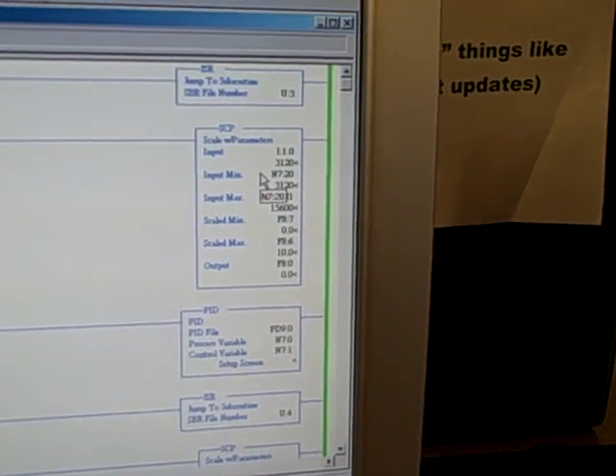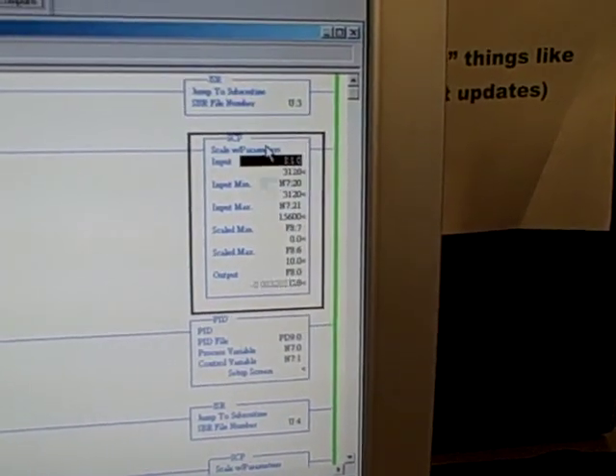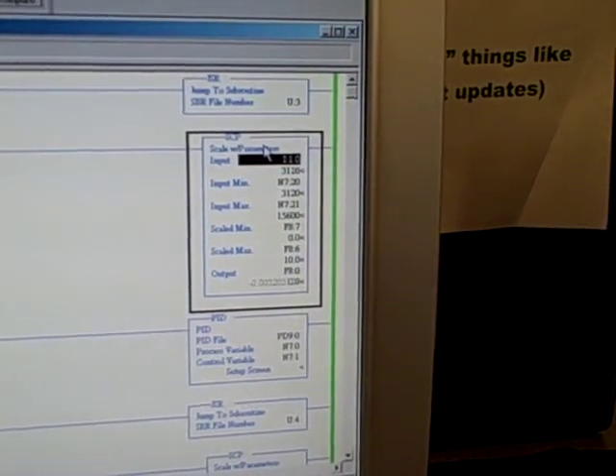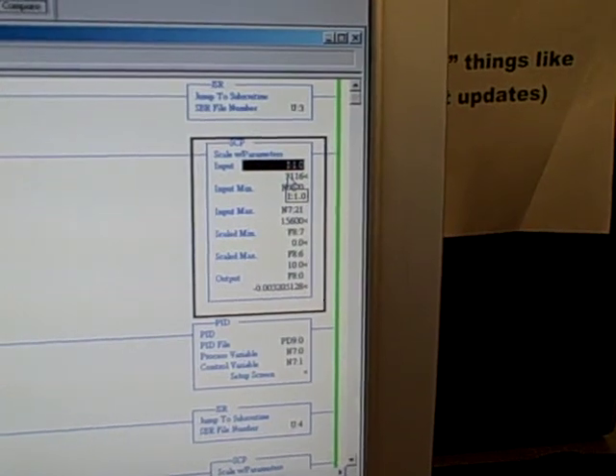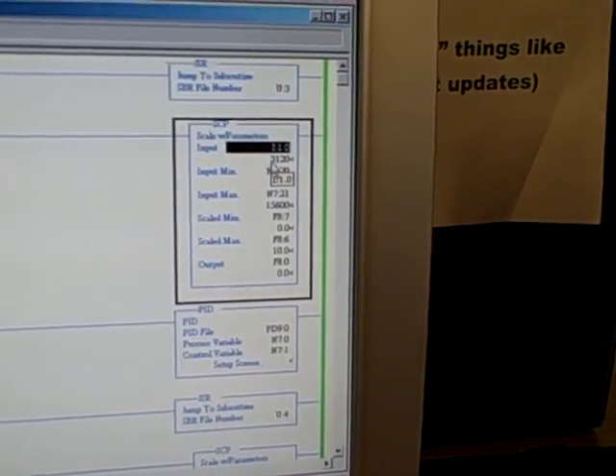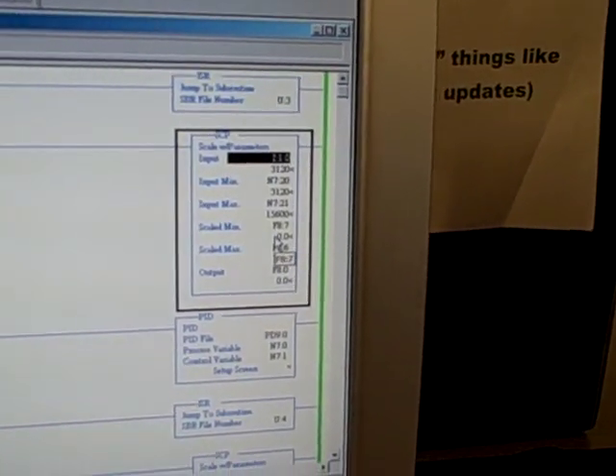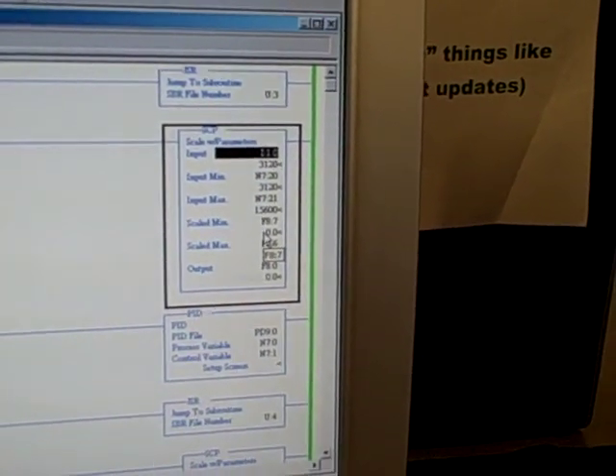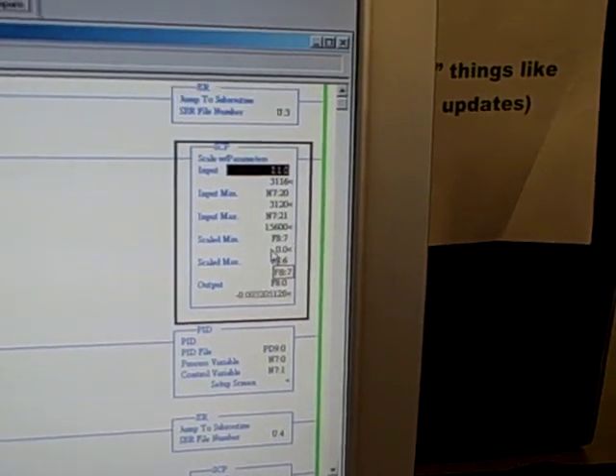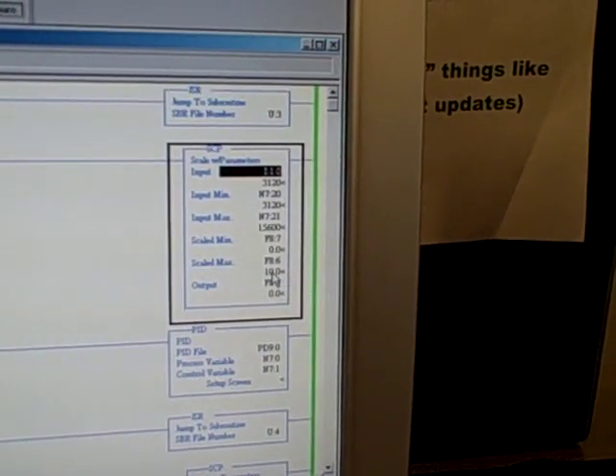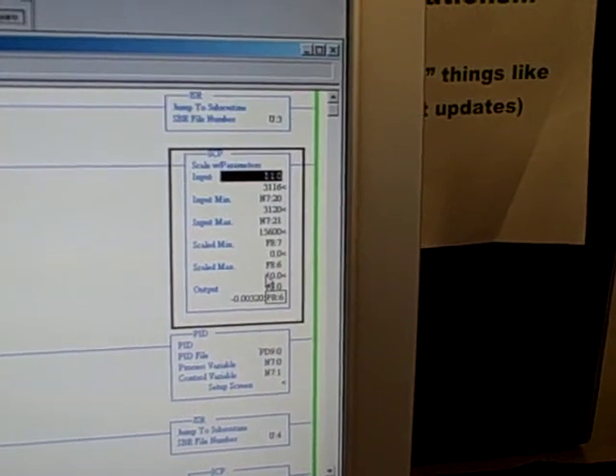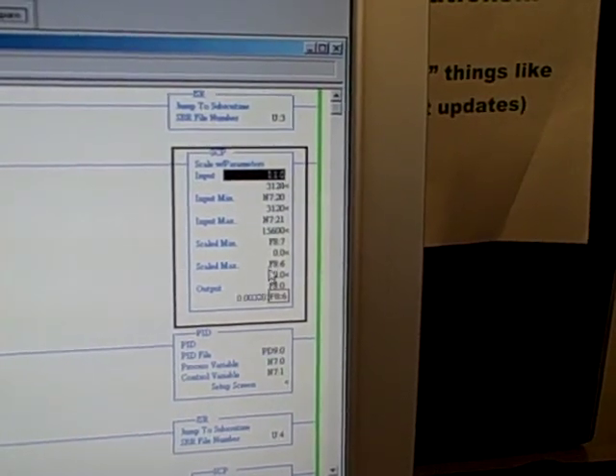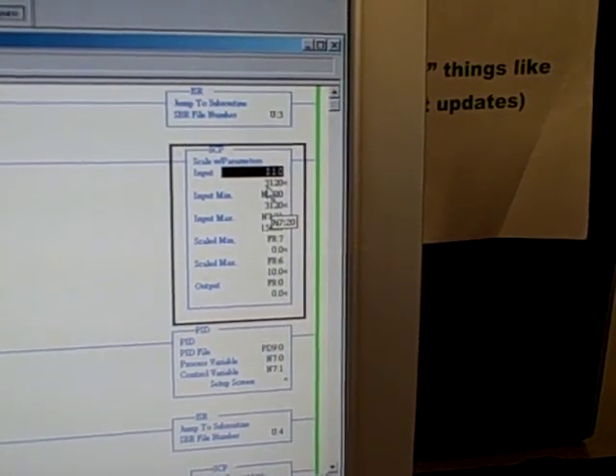Let's pretend we're going to work on loop number 0. The scale parameters right here takes the raw count value from our analog input card, and it scales it to whatever engineering units we desire. This particular team has scaled theirs to output 0 to 10, representing 0 to 10 PSI of pressure in their process.